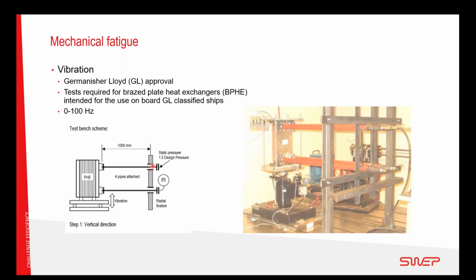The heat exchanger and the pipes are then loaded with a static pressure of 1.5 times the design pressure with a fluid. And then you have the vibration, as you will have quite high loads here on the connections, at the interface between the connections and the connection plate or the cover plate on the heat exchanger. And this is then tested in both directions. And it's a fixed test scheme going from 0 to 100 Hertz. And then, depending on the weight of the heat exchanger or any other object that's tested, it's also setting the amplitude of the acceleration forces on the vibrations.